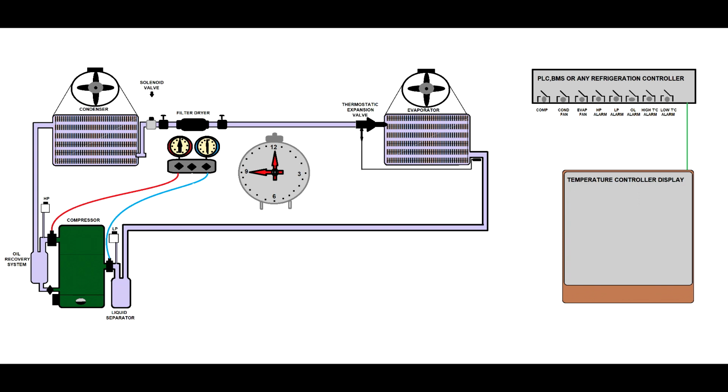Now you have to wait to see if the pressure is dropping. The time is related to the size of the system. So let's say you have a leak. You have to identify the leaks. You can use a leak detector, an electronic leak detector, or a bubble leak detector. And you have to identify all leaks and repair them, because you're not allowed to put refrigerant into the system while the system presents leaks. So that's the toughest job, especially if you have a long run of piping.